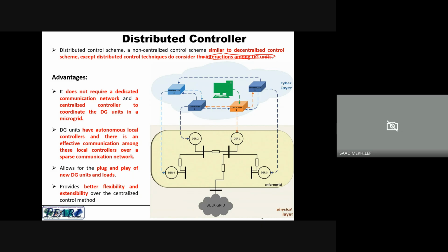And what you can see here, it does not require additional or dedicated communication networks, or a centralized controller to coordinate the DG units in the microgrid. So here we have the bulk grid, and then we have the DGs connected, and then we have the controllers. Each DG has its own controller, but these controllers actually communicate with each other. So there is an interaction between the controllers. This is what we call the cyber layer, and this is the microgrid.